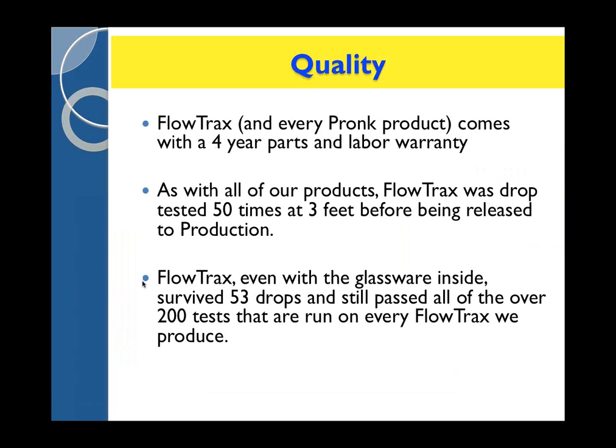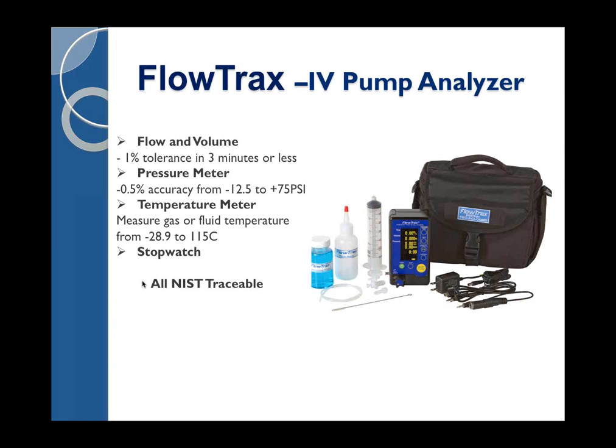So on the quality side of it, Trax and every other product that we've designed comes with a 4-year parts and labor warranty. As with all of our products, it was drop tested 50 times at 3 feet before being released. Even with the glassware inside the Trax, it survived 53 drops and passed over 200 tests after those drops and passed within specification everywhere. The specs, real quickly, are 1% tolerance in 3 minutes or less for flow and volume, 0.5% accuracy of reading from minus 12.5 to 75 psi. The temperature meter range is good from minus 28.9 to 115 degrees C.